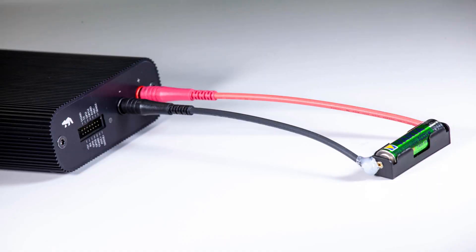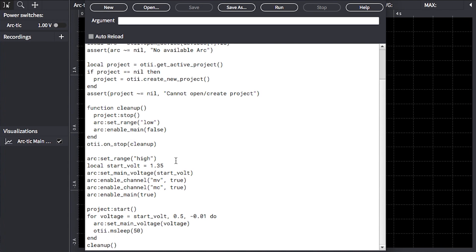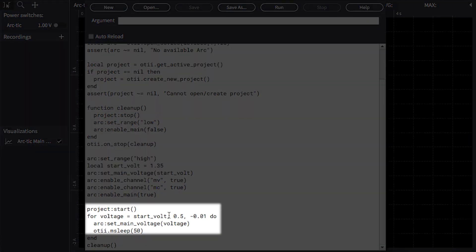To demonstrate this, I've hooked up a AA battery to the main terminals of the Otii Arc, and I have a small script here that will ramp the output voltage set point from just above the battery voltage to almost a volt below, as you can see in this loop here.